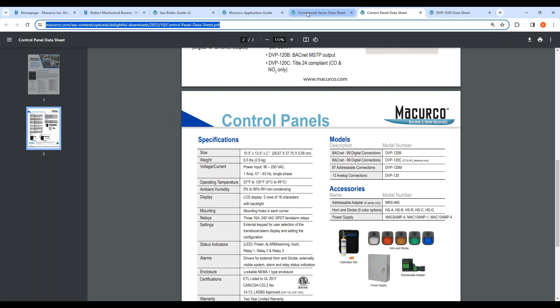Well, the only thing I would add is the T-tap comment is field T-tap. You can actually, in the control panel, have multiple wires, a couple of wires under each output terminal of the MRS 485. Correct. You can't put 192 like in that picture right there on one pair of communication wires. We're limited to 3 outputs in that controller, and each output will handle 64 sensors. Correct. So, just kind of keep that in mind. You're not putting all 192 on one pair of wires. It would tend not to work.